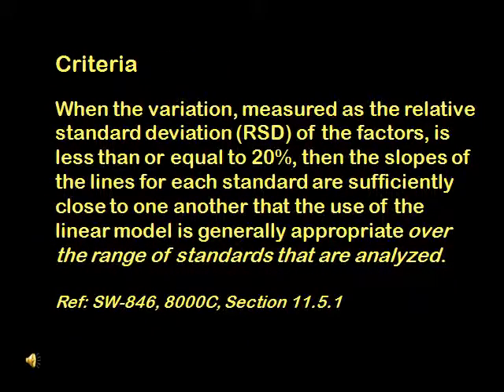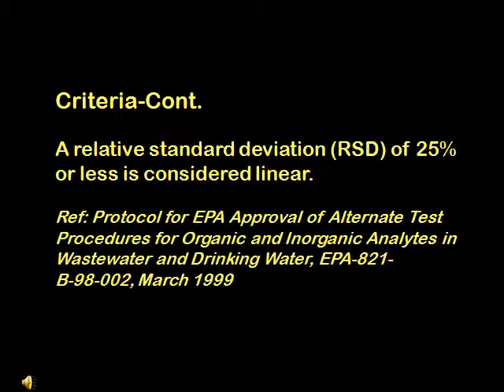Common criteria specified by EPA is that the RSD of the factors is less than 20% in order to use the average RF or CF for calculating concentration. Do note that some methods specify more stringent criteria. For example, EPA method 1631 for low-level mercury specifies a less than or equal to 15% RSD for the calibration factor. And some references do accept a wider RSD criteria of 25%.